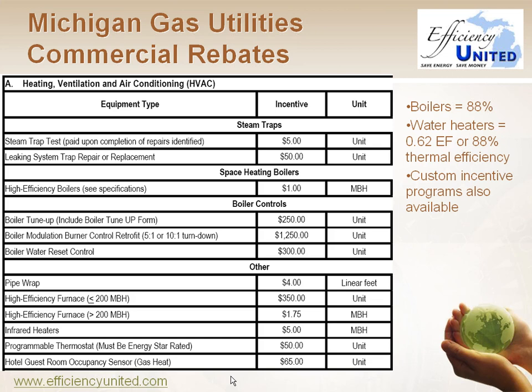In Michigan, the Michigan gas utilities have a program. It's called Efficiency United, and that's the website, efficiencyunited.com. The boilers have to be 88% efficient, so that fits in line with some of these other programs. And you'll see that you get $1 for every 1,000 BTUs. So in this case, a 1,000,000 BTU boiler would get you $1,000 rebate. And then they also have the boiler water reset controls for outside air reset, which is $300 per boiler.